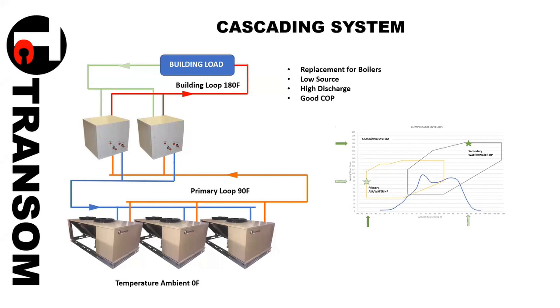Have you ever explored the idea of working with CSA or AHRI to work on a cold climate test procedure specifically for your types of products? You know, it tends to be a fairly new application. So it hasn't really gelled. There haven't been too many common applications. Each one is slightly different, right? So say we do these ones and then somebody wants to locate it in the garage. So then we switch actual fans to blowers so we can duct it outside so you don't get short circuiting on the airflow. And so that would negate your ARI, because even the shape and size of the unit.